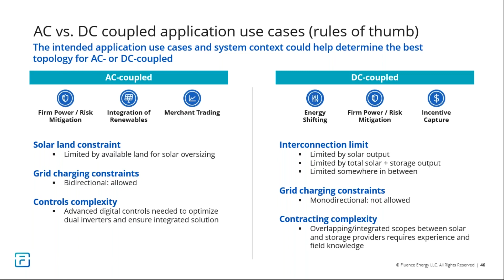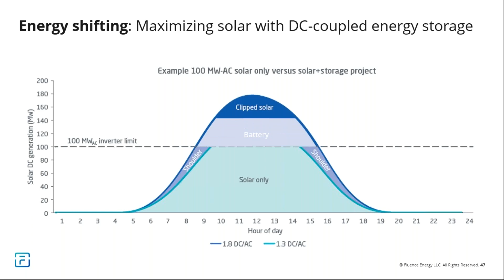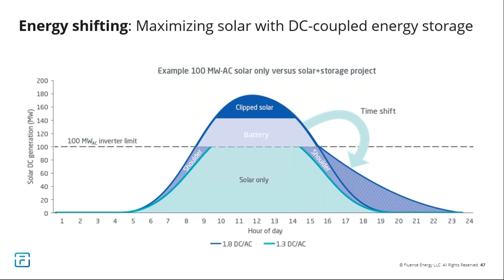I'll go through this graphic quickly to highlight the value of DC coupling for energy shifting. With a standard solar 1.3 DC generation capacity to inverter AC capacity ratio, you get a little bit of clipped energy, which isn't worth much. But if you oversize further, up to a 1.8 or even 2.5 ratio of solar capacity to inverter, you get a significantly larger amount of clipped energy, and that's where DC coupled storage can really provide value. The vast majority of that clipped energy goes straight into the battery, which can then be time shifted to extend solar generation later into the evening during peak periods.